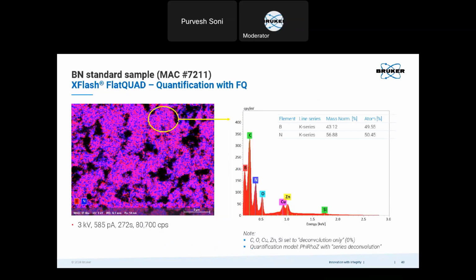And this is a boron nitride standard sample on a brass block. And we can see only 3 kV measurement and very low probe current and still very high count rate. And after quantification, we can see boron and nitrogen, they are 1:1. Of course, I set carbon and oxygen and the other contaminants as deconvolution only. So then they are automatically set to 0%, giving me boron and nitrogen quantification only at 1:1 stoichiometry.